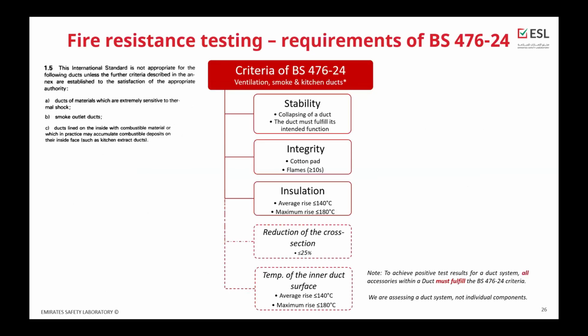What are the criteria for the ducts, ventilation, smoke, and kitchen ducts as per BS 476 part 24? We have three main criteria which are described in the standard: stability, integrity, and insulation.